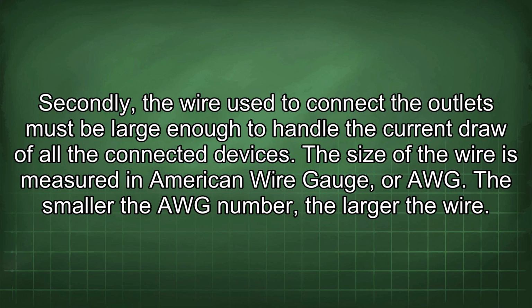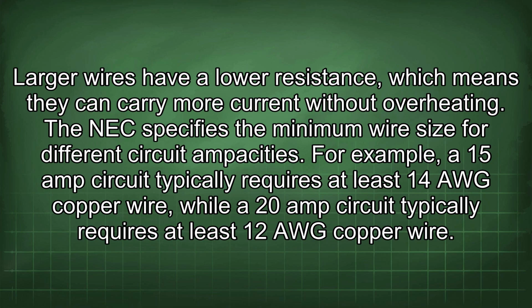the connected devices. The size of the wire is measured in American wire gauge, or AWG. The smaller the AWG number, the larger the wire. Larger wires have a lower resistance, which means they can carry more current without overheating. The NEC specifies the minimum wire size for different circuit ampacities. For example, a 15 amp circuit typically requires at least 14 AWG copper wire, while a 20 amp circuit typically requires at least 12 AWG copper wire.